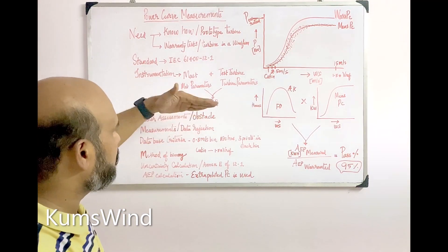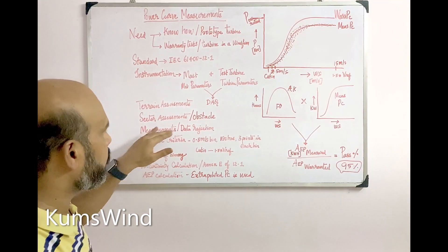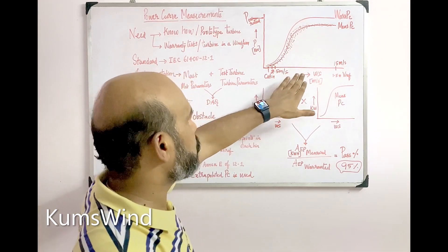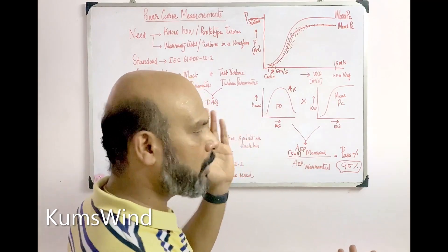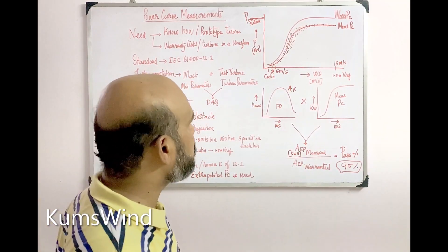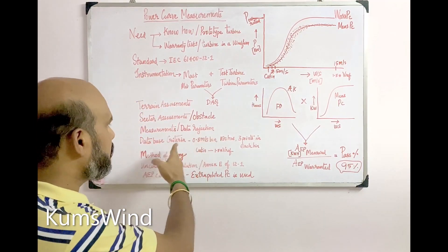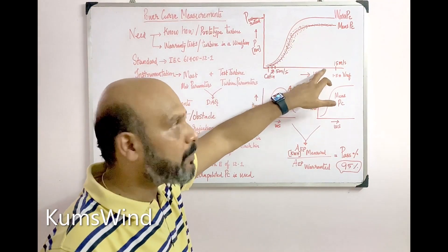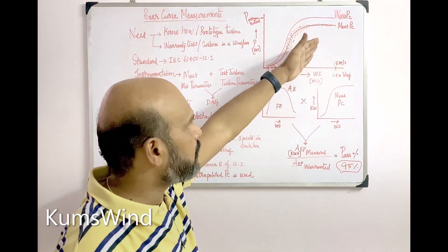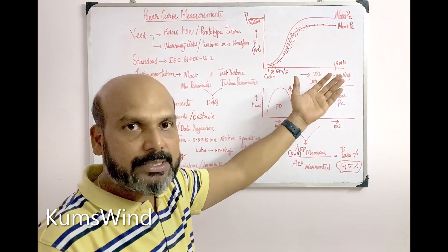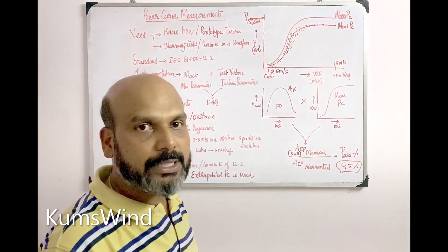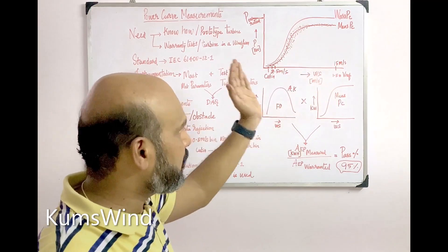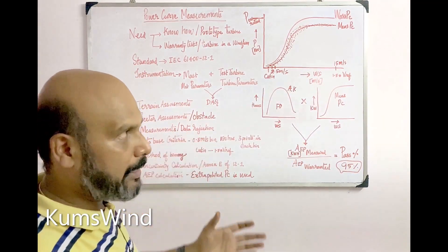IEC 12-1 clearly explains the process, gives requirements for the slopes, and provides the formula to calculate the measurement sector. The measurement involves measuring wind speed, power, and supporting parameters like humidity, temperature, pressure, and operational status. These are needed for proper data rejection and filtering, because there may be instances where the turbine is stopped even though the wind is high — due to breakdown, maintenance, or other reasons — and such data has to be eliminated.